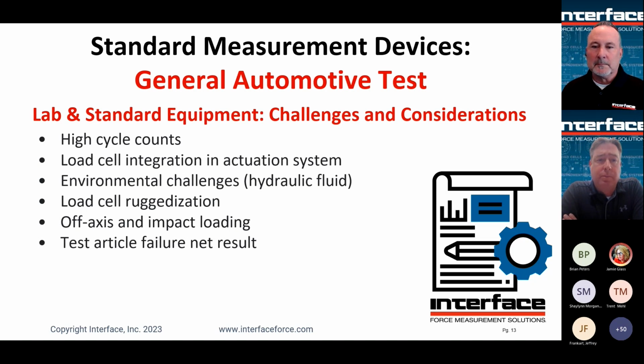Load cell ruggedization. That's another one where you have tests getting configured, tests getting taken down. Essentially, you're going to be setting up for multiple tests over the life of your equipment, and you're going to be moving actuators, moving load cells. It's not uncommon for someone to trip on a cable or kick a cable, drop a wrench. So the ruggedization of the load cell can be important. So you can do that a couple of ways. There's specific features you can add to the load cell, such as connector protectors, where you can actually spec in a load cell with the expectation that it's going to be in a rough environment. So maybe you want a welded stainless steel unit, things like that.